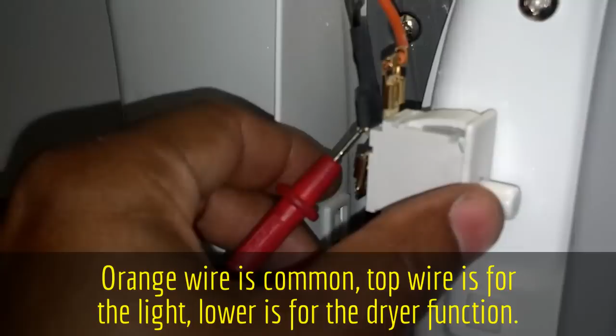So I got my gauge set there, and I'm going to use my hands to put it on these probes. I'm going to put my ground on the black one, or up here on this orange one. Really doesn't matter, you're just checking resistance. Then I'm going to hit the other one on here, holding one here and the other one up top, and check my ohm meter.